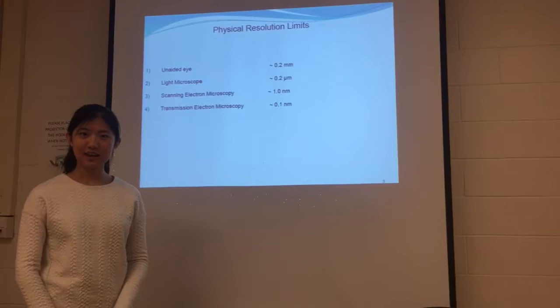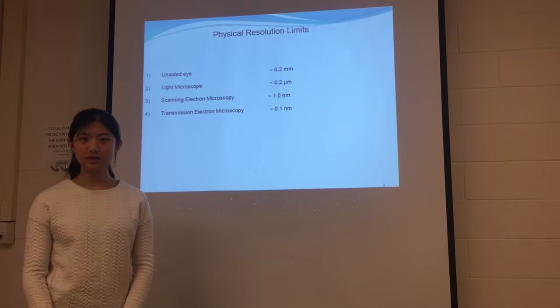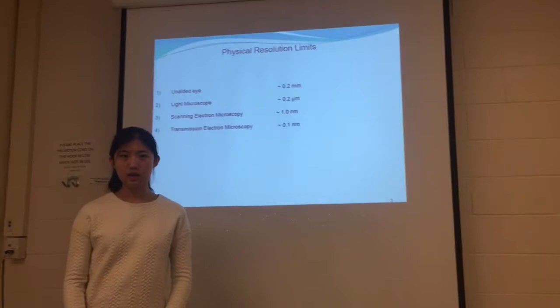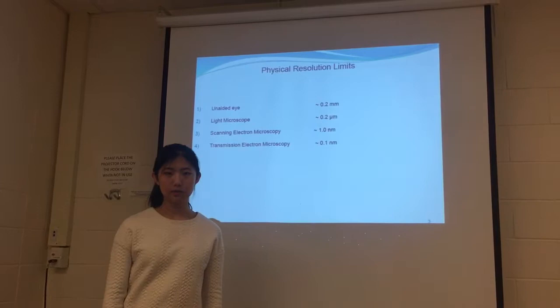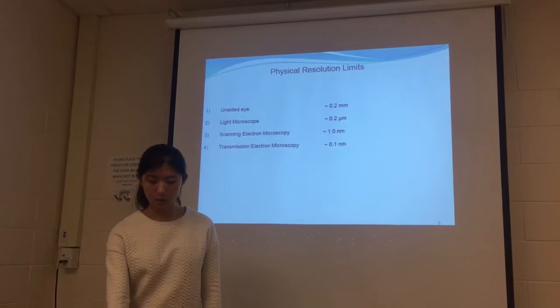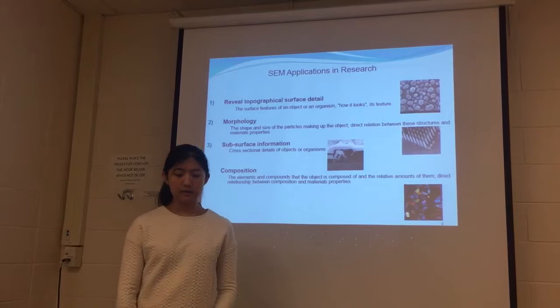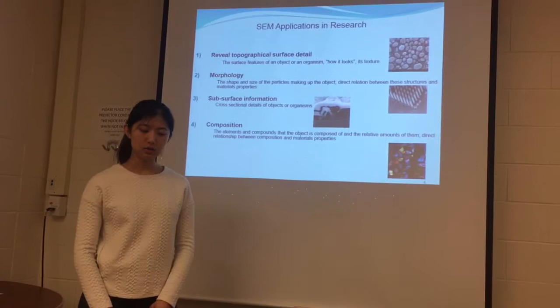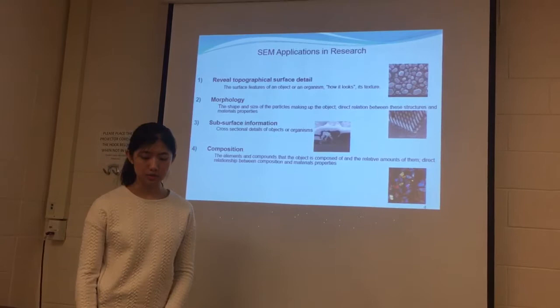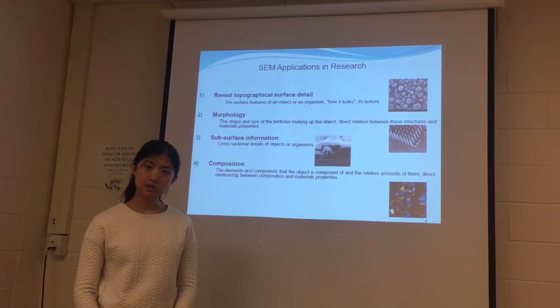Theoretically, the SEM can achieve very high resolution, about one nanometer, but due to the charging effect, we cannot reach that high resolution. We always use it to look at structures of over 50 nanometers. When we need the precise nanostructure of samples, we use TEM, which has a higher resolution of about 0.1 nanometer. SEM has a lot of applications in research — it is highly used to get topographic surface details, morphology, thickness, subsurface information from cross-section SEM, and also the composition of your specimen.